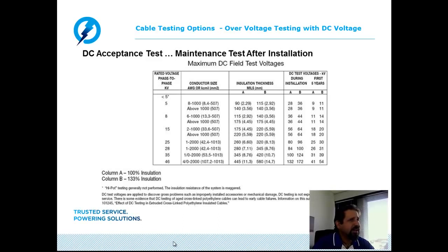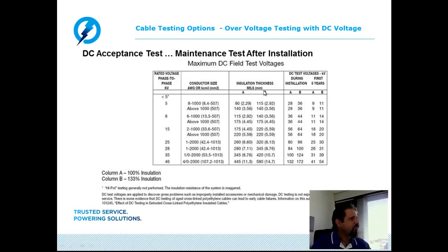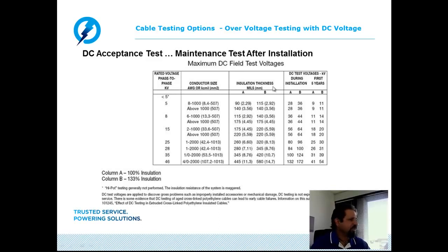DC acceptance tests for installation and acceptance: this chart, taken from Okonite's website, shows that DC is still called out for installation and acceptance testing. It provides guidance on DC voltage levels to apply based on the phase-to-phase kV rating and conductor size. Notice it clearly states for the first five years — meaning after service age or after five years, even Okonite is indicating DC testing should no longer be applied.